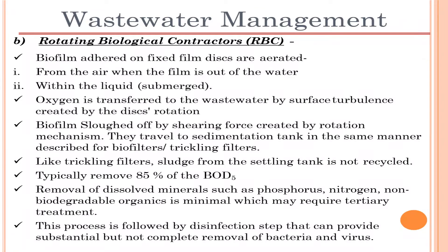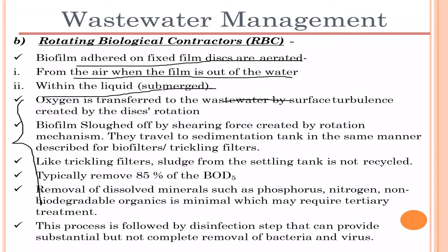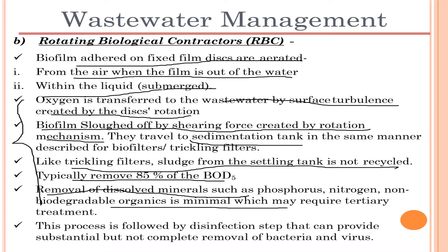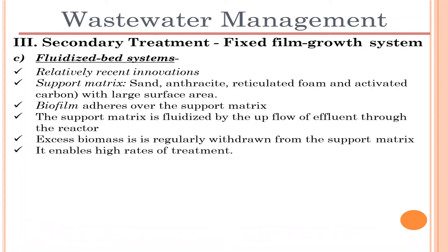The biofilm attached to the fixed film is aerated from the air when the disc is out of the water and receives nutrients when submerged. Oxygen is transferred to the wastewater by surface turbulence created by disc rotation. Biofilm is knocked off by the shearing force created by the rotation mechanism and travels to a sedimentation tank, similar to trickling filters. Sludge from the settling tank is not recycled. This process typically removes 85 percent of BOD5. Removal of dissolved minerals such as phosphorus, nitrogen, and non-biodegradable organics is minimal and may require tertiary treatment.